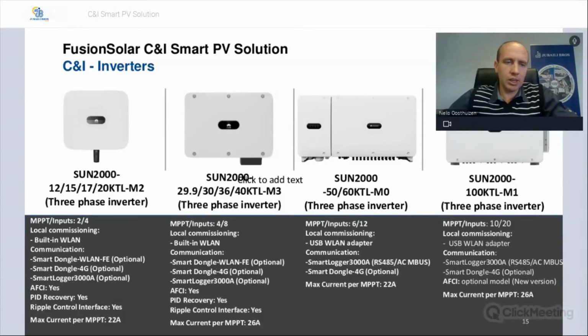It's got built-in WLAN communication, can do smart dongle WLAN communication, 4G communication, and it can also communicate with a smart logger. It's got built-in AFCI as well as built-in PID recovery, and it's also got ripple control interface if it's a requirement from your utility. The maximum current per MPPT would be 22 amps.